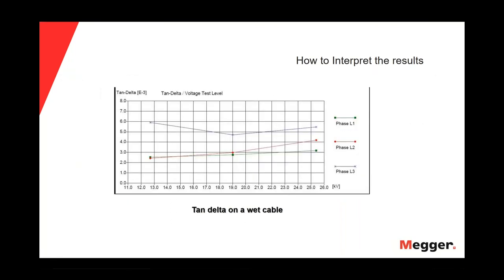and this one is a really interesting graphic, because if you see phase L3, we start with very high values of the tan delta, but as we increase the voltage, the tan delta decreases, which is not common. It's a little strange for the tan delta, because we would expect that as we increase the voltage, the values of the tan delta remain the same or increase a little bit. But in this case, the values decreased as we increased the voltage. What happened in phase L3 is that we have some water, and when we put some current in the cable during the tan delta test, some of that water dried out, and for this reason we start to get lower values for the tan delta. Okay?